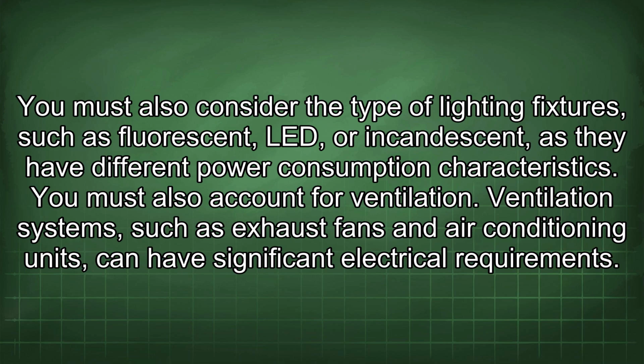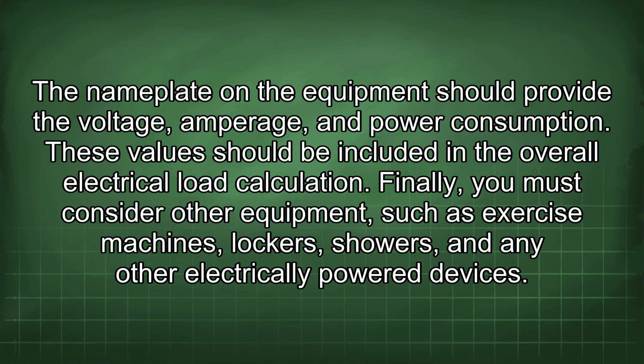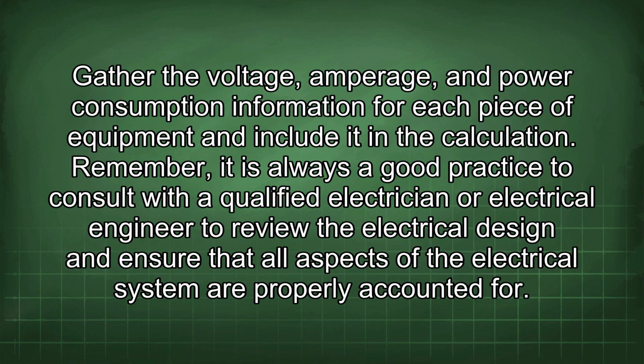You must also account for ventilation. Ventilation systems, such as exhaust fans and air conditioning units, can have significant electrical requirements. The nameplate on the equipment should provide the voltage, amperage, and power consumption. These values should be included in the overall electrical load calculation. Finally, you must consider other equipment, such as exercise machines, lockers, showers, and any other electrically powered devices. Gather the voltage, amperage, and power consumption information for each piece of equipment and include it in the calculation.